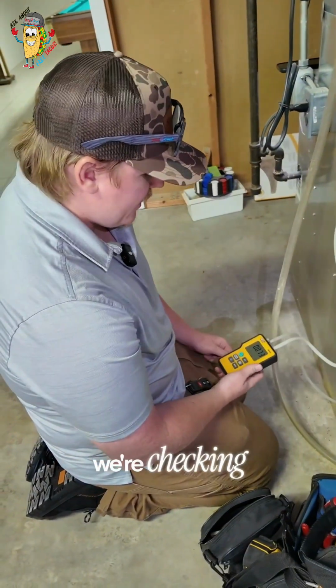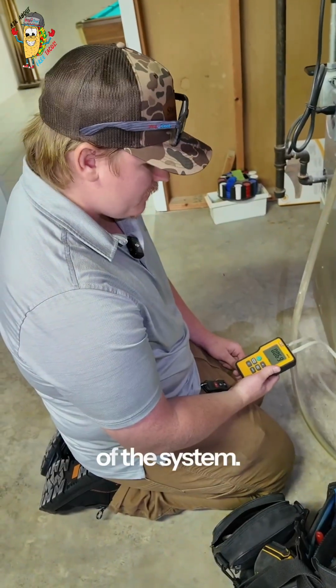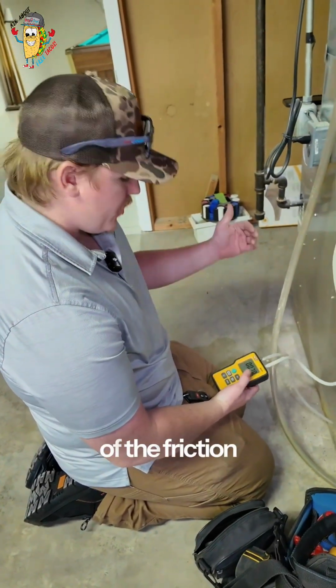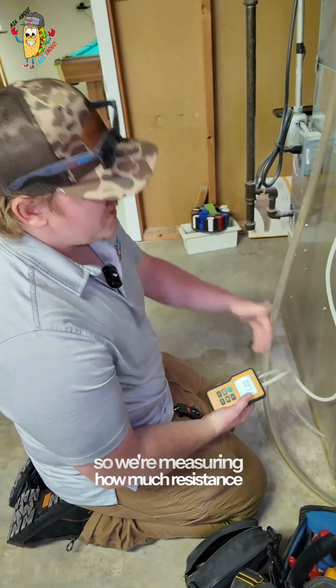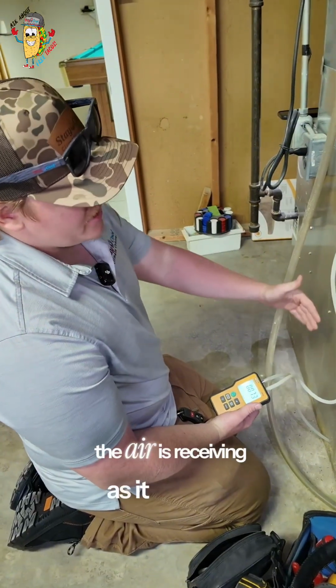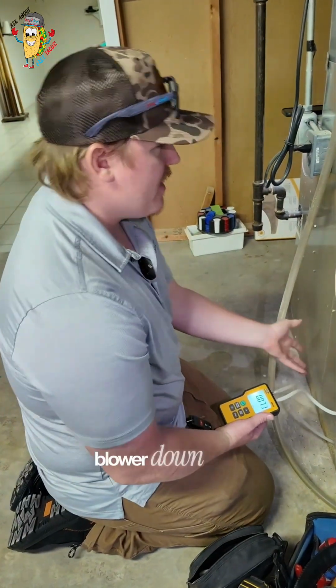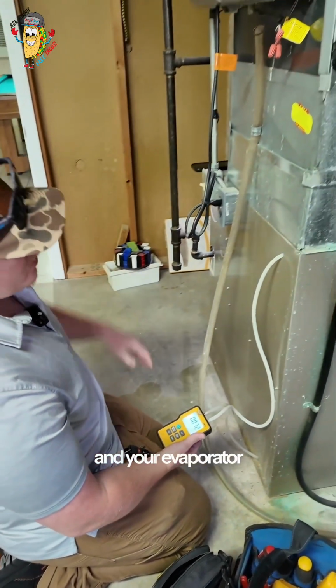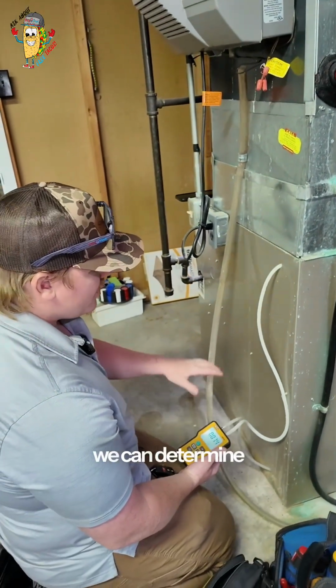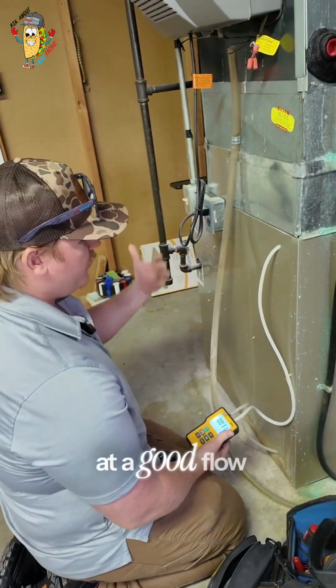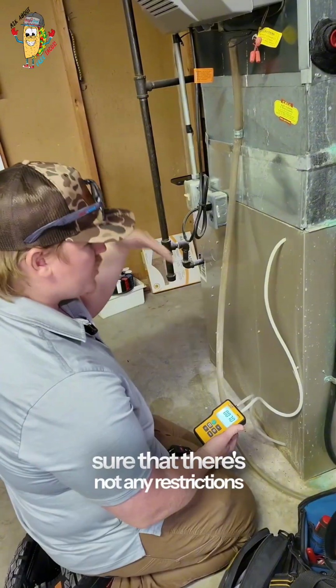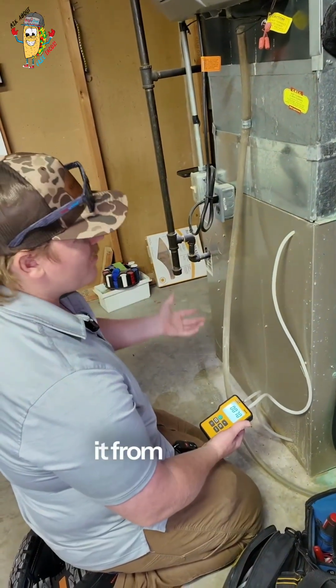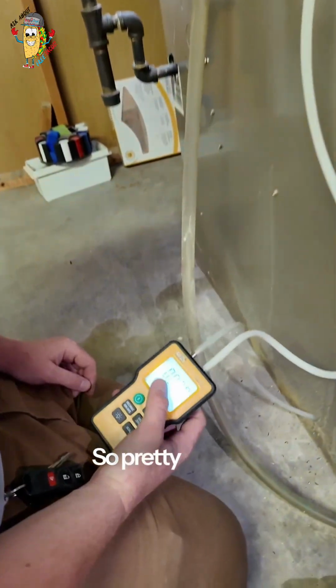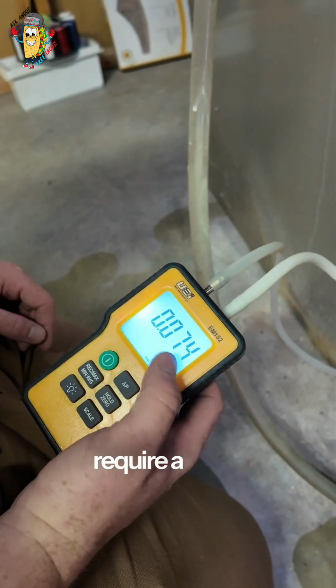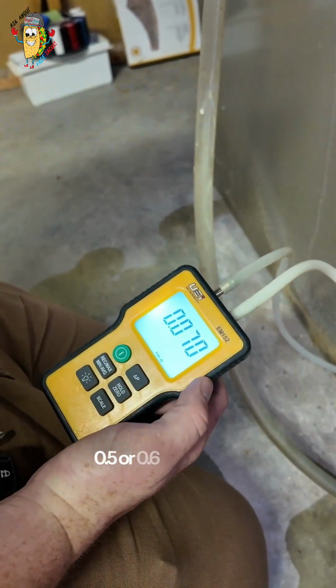Right now we're checking the static pressure of the system. Static pressure is basically a measurement of the friction of air. So we're measuring how much resistance the air is receiving as it travels through the furnace. So you have your blower down here, your heat exchanger, and your evaporator coil. By taking the static pressure, we can determine that air is moving at a good flow rate and make sure that there's not any restrictions or things that are going to prevent it from getting up to the home where it needs to be. So pretty much most systems require a static pressure of around 0.5 or 0.6 maximum.